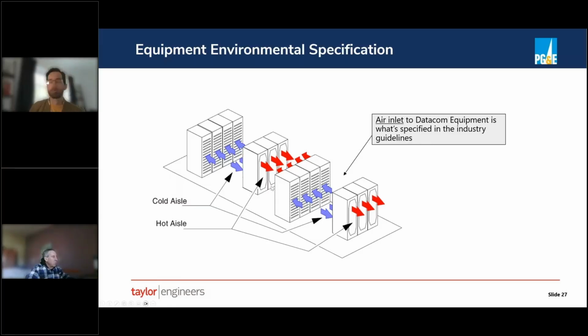servers in what we call hot aisle, cold aisle. The fronts of the computers are all on one side, facing a row of racks that are also oriented to blow into the hot aisle, right? Computers pull cold air from what we call the cold aisle and blow it into the hot aisle. And the mechanical system has to deliver the cold air and then retrieve the hot air. And so what's the condition of the air entering the computers?